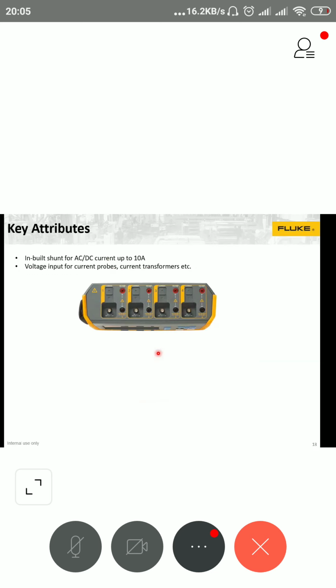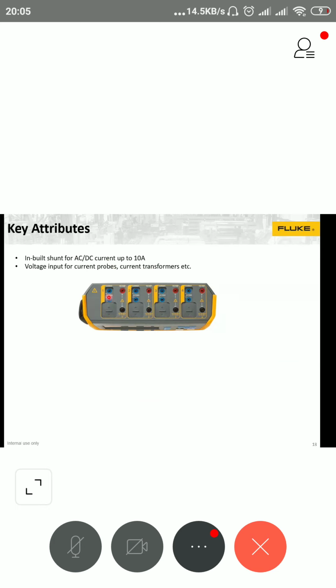Now you can see here, this is a 4 channel equipment. The red and black here indicate the voltage connection. In this voltage connection, you can measure up to 1000 volts. And the blue color indicates the current measurement, where you can measure directly up to 10 ampere. When I say directly, a shunt is available here, up to 10 ampere, so you can measure up to 10 ampere.